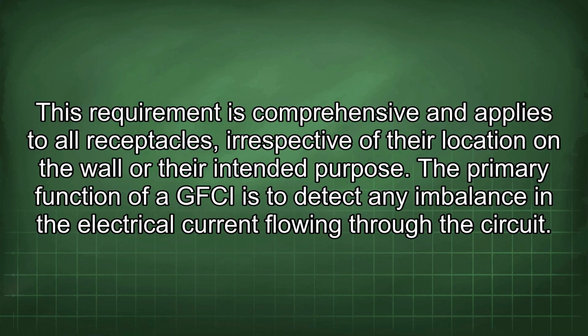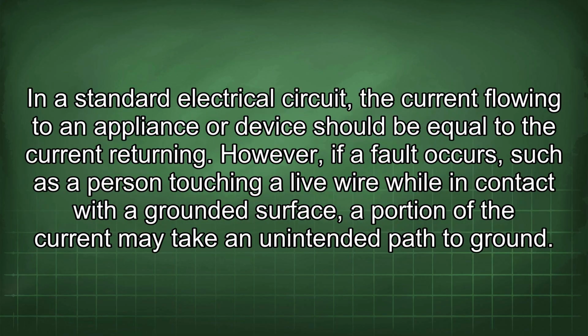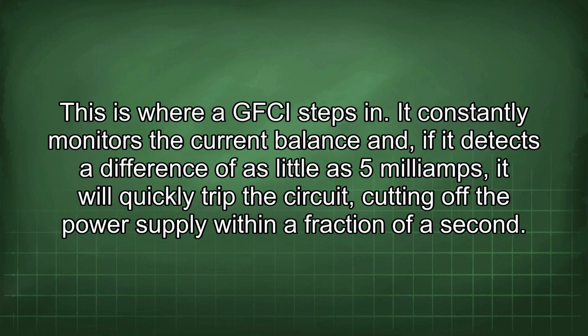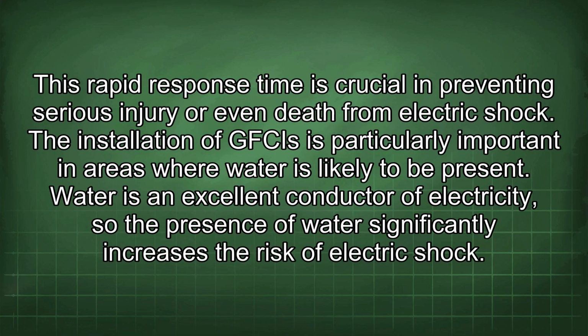The primary function of a GFCI is to detect any imbalance in the electrical current flowing through the circuit. In a standard electrical circuit, the current flowing to an appliance or device should be equal to the current returning. However, if a fault occurs, such as a person touching a live wire while in contact with a grounded surface, a portion of the current may take an unintended path to ground. This is where a GFCI steps in. It constantly monitors the current balance, and if it detects a difference of as little as 5 milliamps, it will quickly trip the circuit, cutting off the power supply within a fraction of a second. This rapid response time is crucial in preventing serious injury or even death from electric shock.